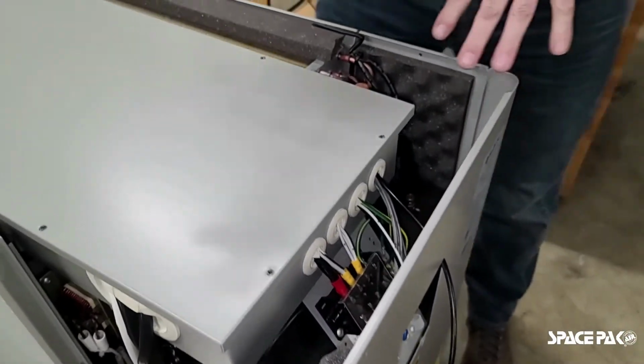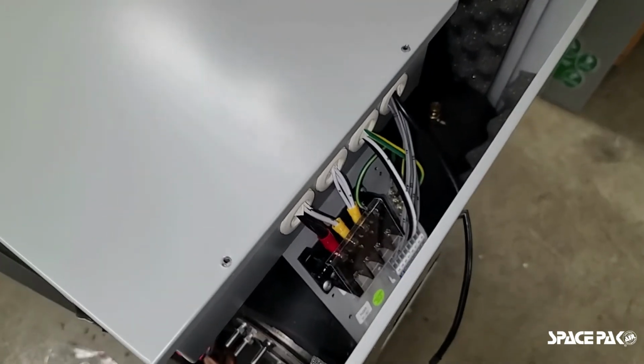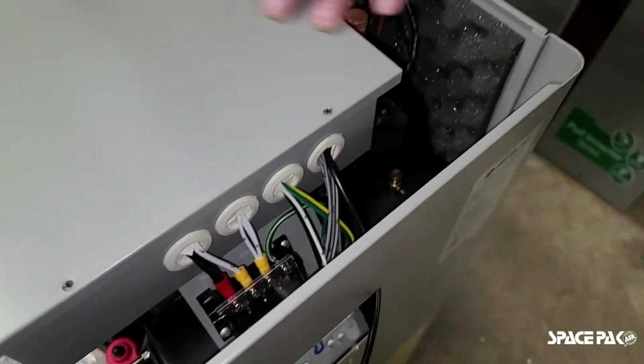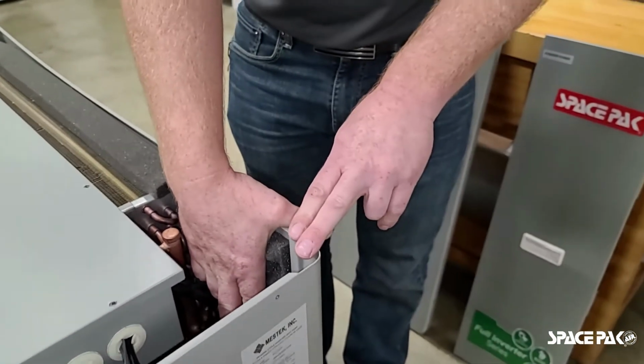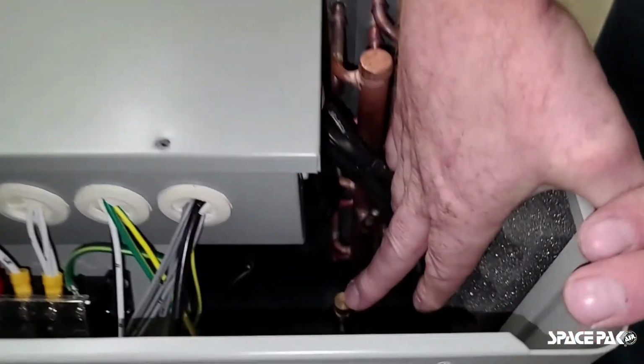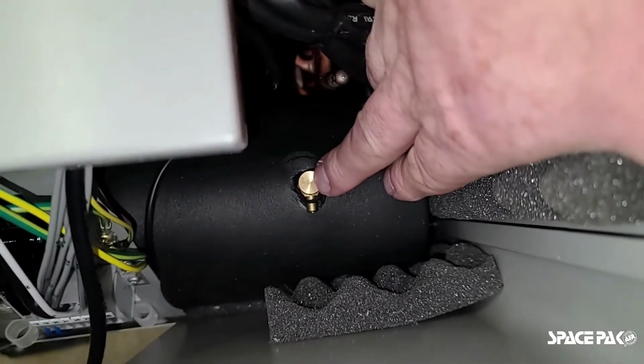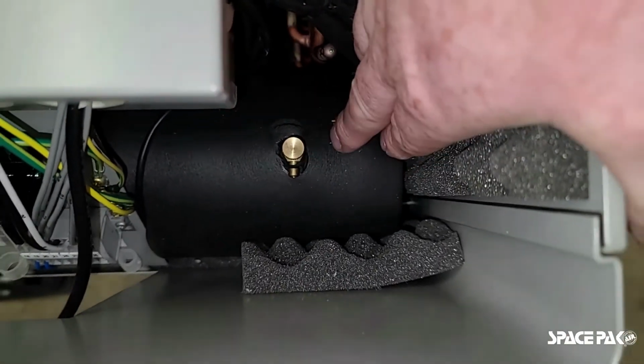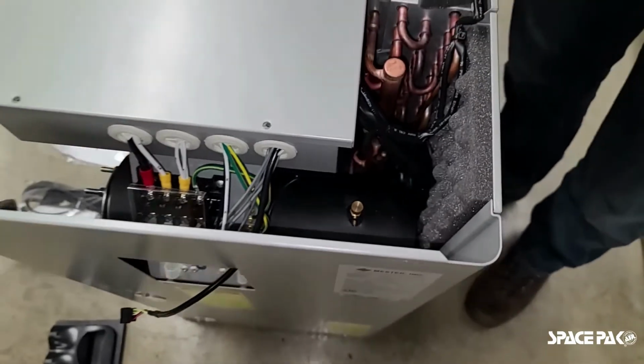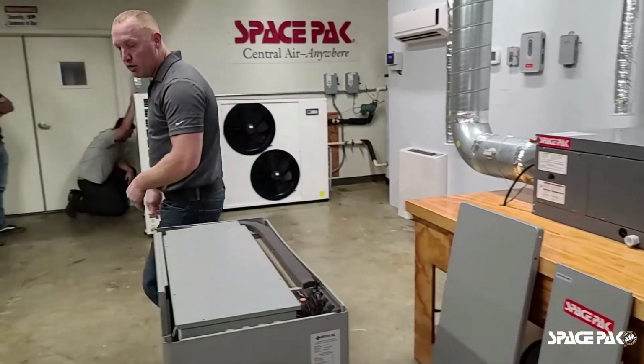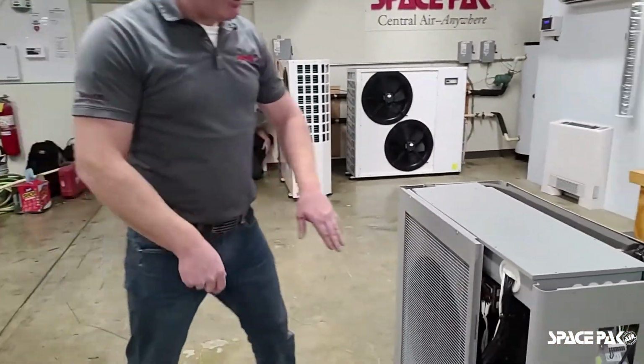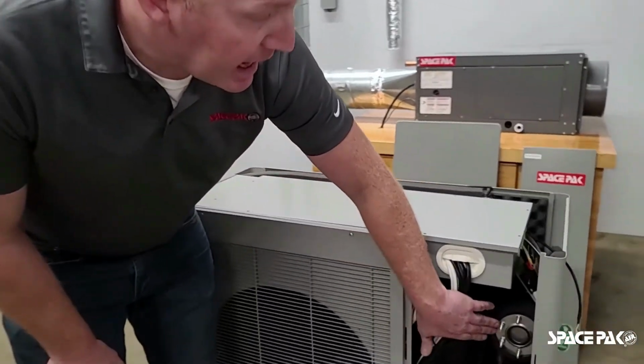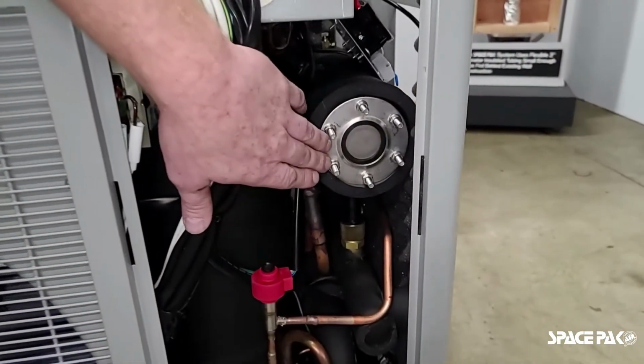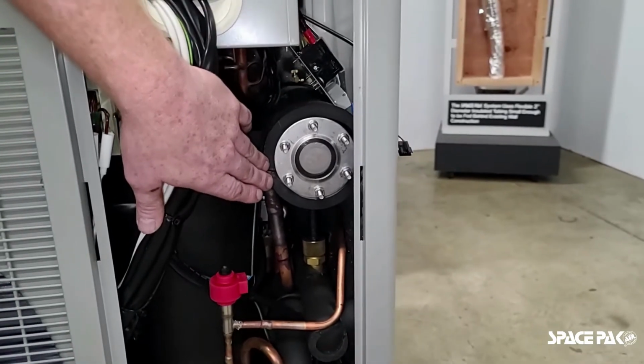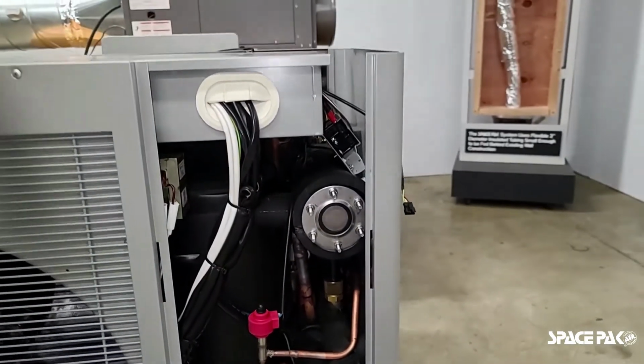As we look down from the top here, when it comes time to commissioning the system and bleeding out air within the system, we actually have a thumb valve air port right here. Put a little rubber hose on that, fish it out, little thumb screw. That'd be the highest, in most situations, the highest part of the system and the best place to get the air out of. Also on this SIM Series 36 model, we have the option to add an immersion well heater, similar to the other 3 and 5 ton series Solstice units.